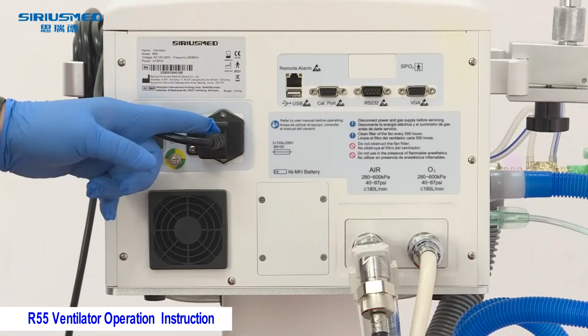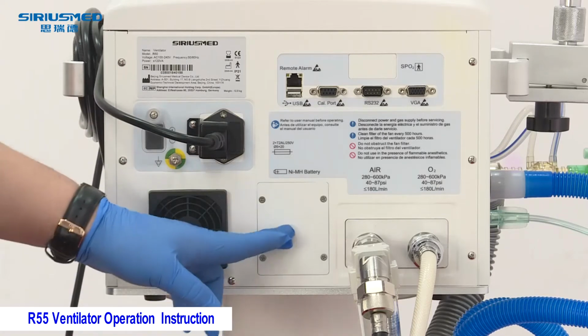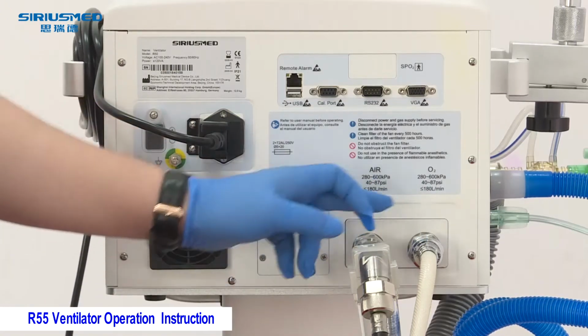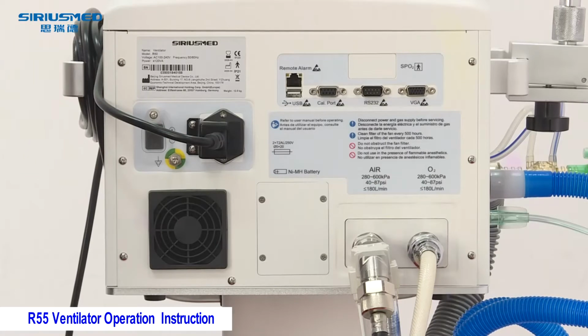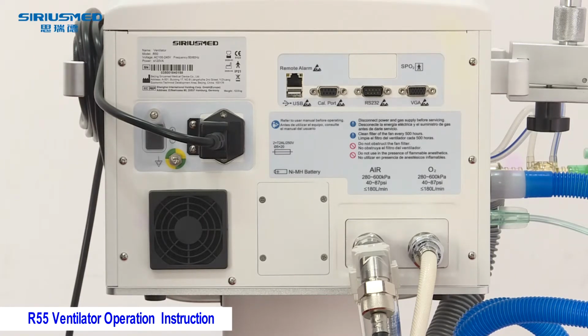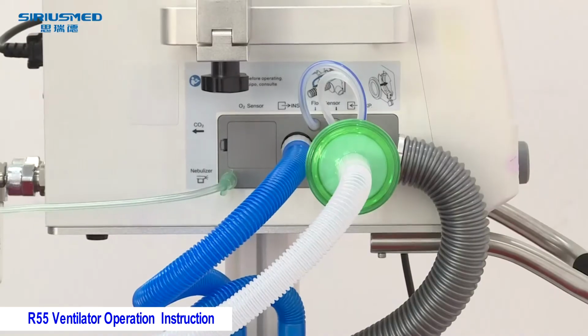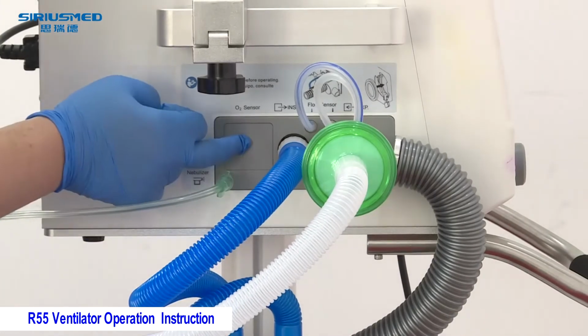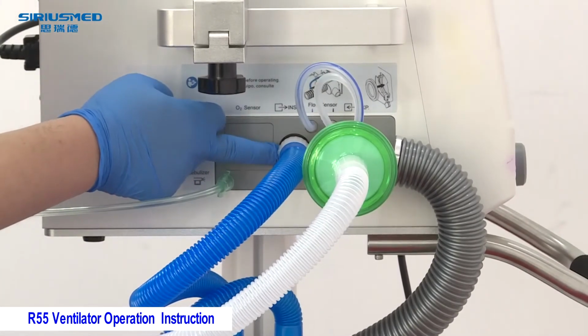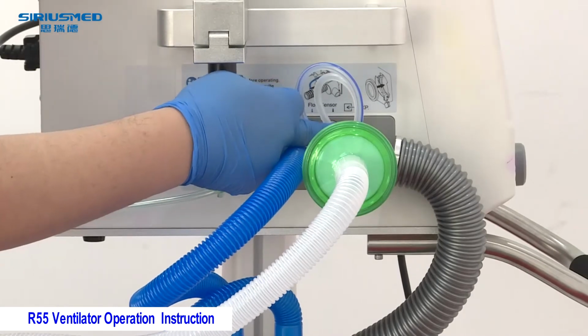Switch, power cable, fans, battery, and gas supply for air and oxygen. The pressure for the gas supply is between 280 to 600 kPa, but for safety consideration, we suggest the gas supply pressure is between 315 to 500 kPa. Nebulizer, oxygen sensor, inspiration port, and expiration port.